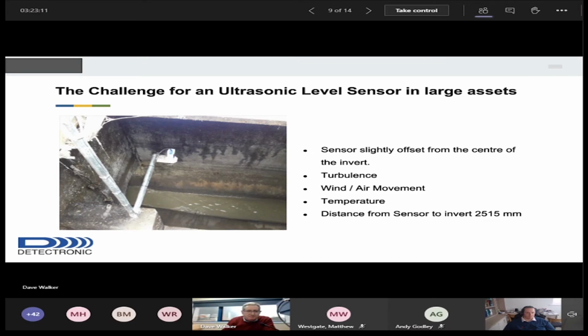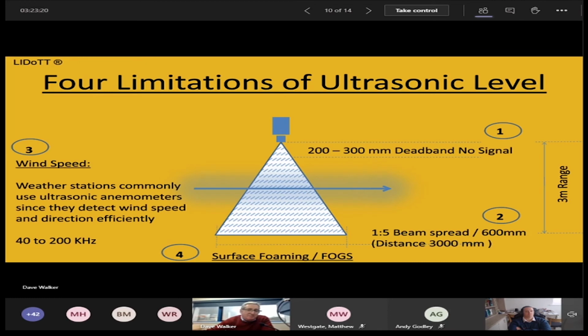So, four limitations of ultrasonic level sensors. As I mentioned, 200 to 300 mil deadband. I'm going to run through this quickly because Alistair McKinnon's coming on and he knows all about ultrasonic level sensors. A 200 to 300 millimeter deadband is typical, where any water going into that deadband means the sensor is what we'd call blind. The instrumentation manufacturers of ultrasonic level sensors are improving that deadband and the beam spread, which is at the bottom there. 1 in 5 beam spread typically, so at 3 meter range you're looking at 600 mil beam spread. Again, we are improving the angle and the beam spreads, but let's stick here with the traditional ultrasonic level sensors.